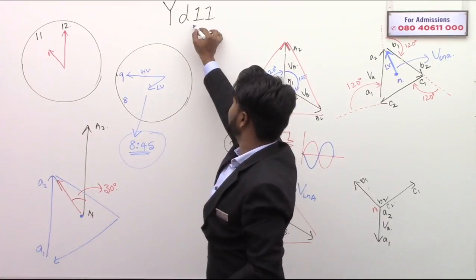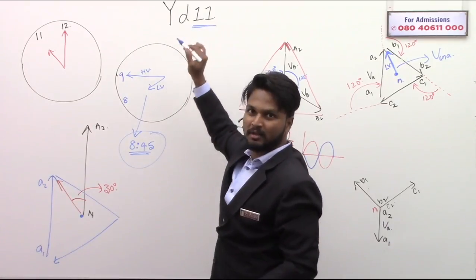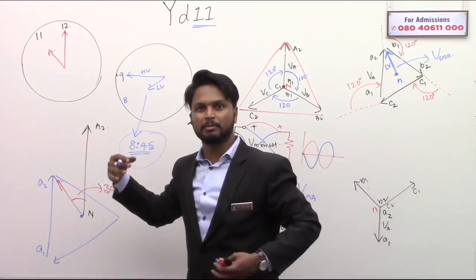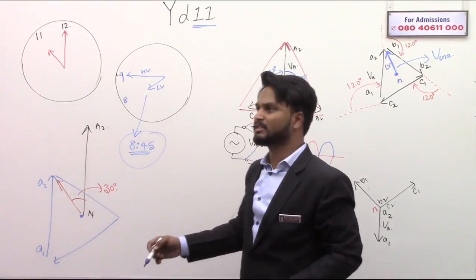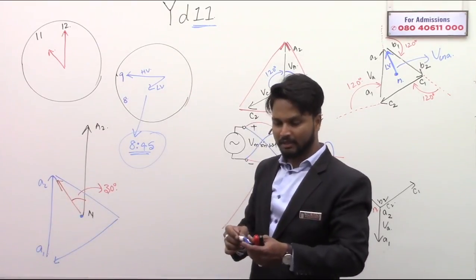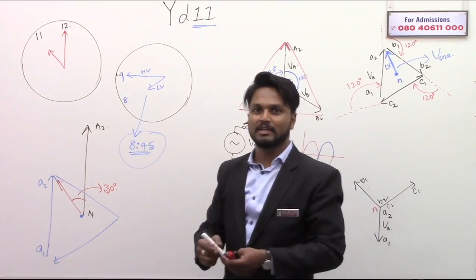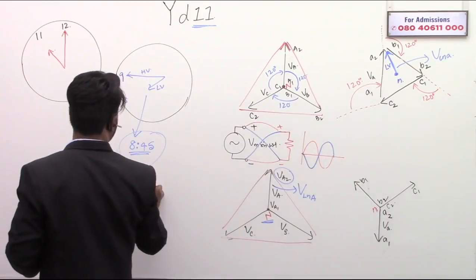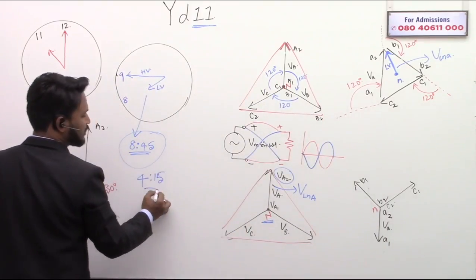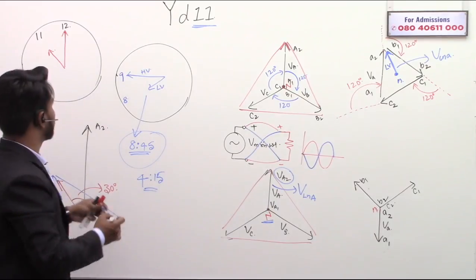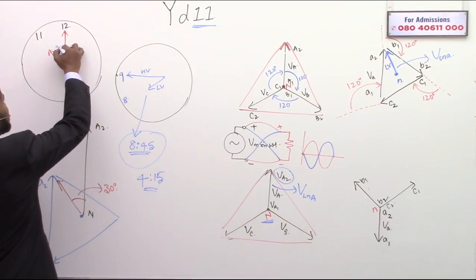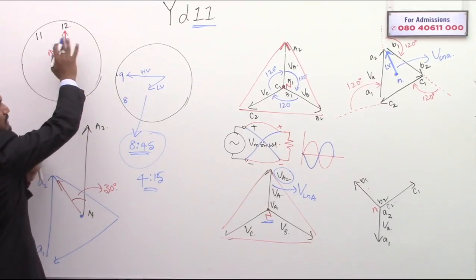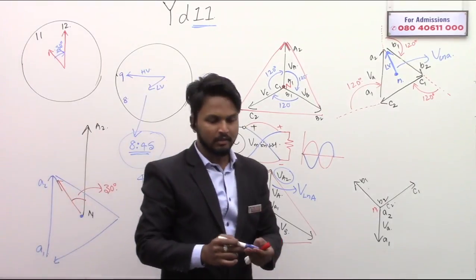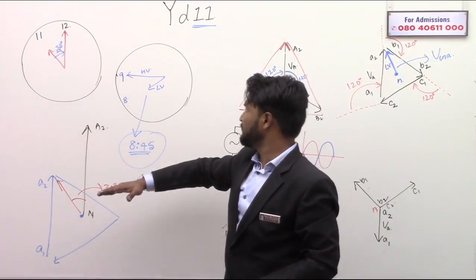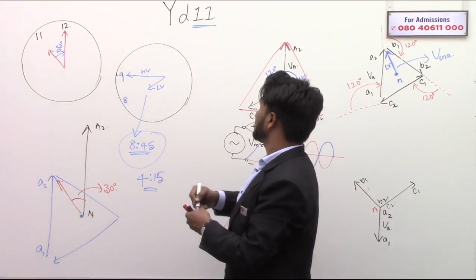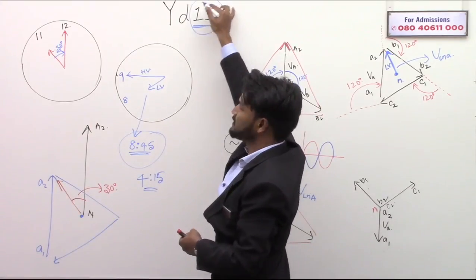I am representing it as 8:45. Someone else is representing it as 11, and someone else as 4:15. All these are possible for the same configuration. The difference is only in how we indicate the phase difference of 30 degrees -- we can use the simplest notation. So if we bring the HV side phasor to the 12 o'clock position, we can give the representation in the simplest manner. That's it.